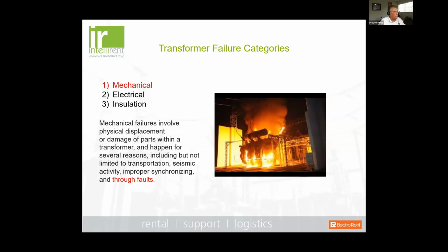And for this reason, we put vibration monitors on them that are sensitive if this should happen. But it's not limited to just transportation. Seismic activity can cause physical damage. Improper synchronizing of a generator, a GSU, would absorb a lot of mechanical force if we were attempting to synchronize that generator 90 degrees out, which would cause excessive damage. But the one thing we want to talk about today is through faults.